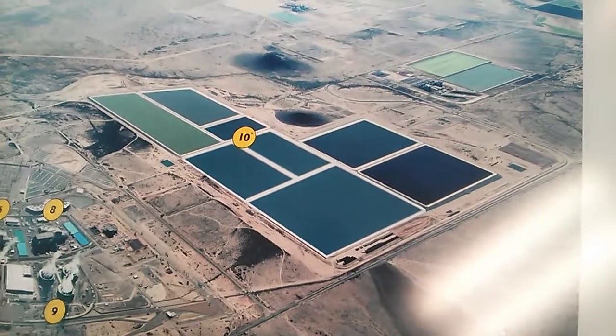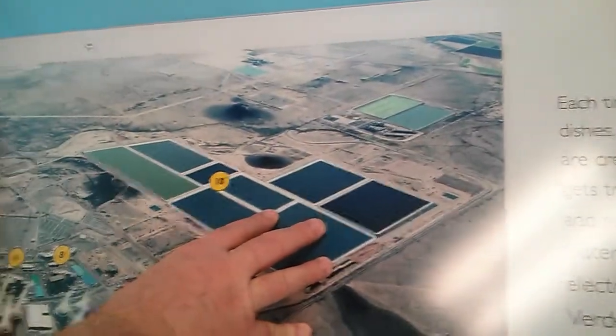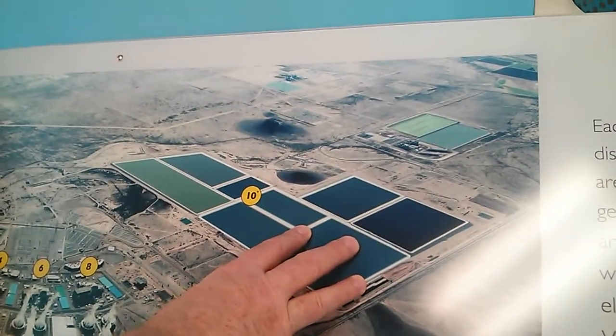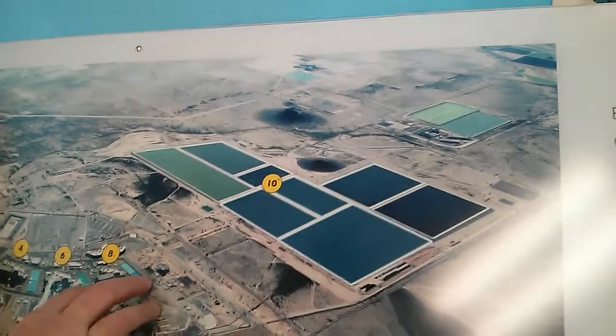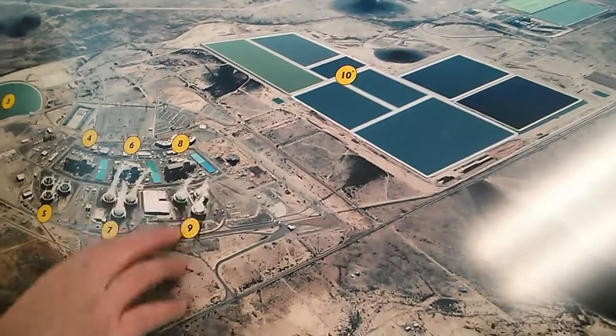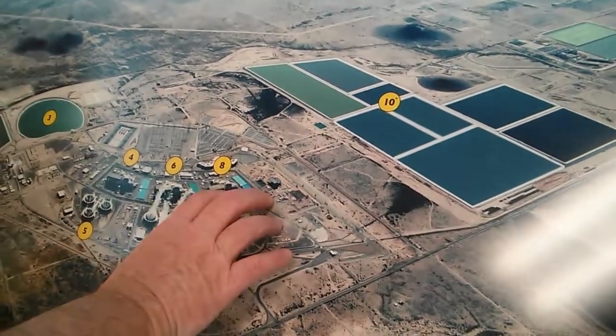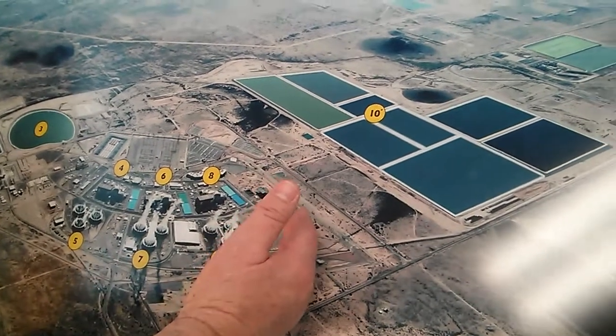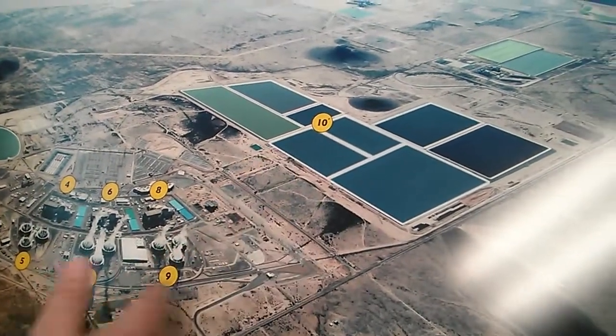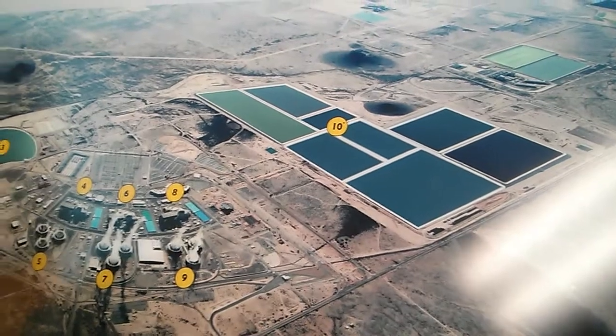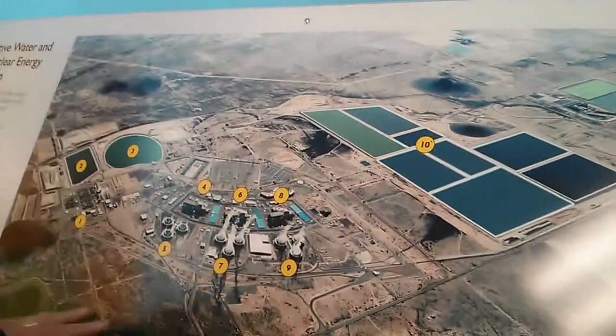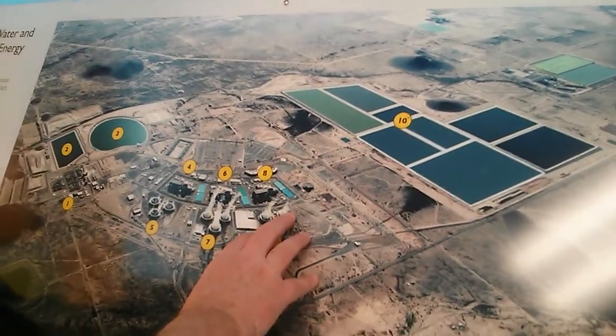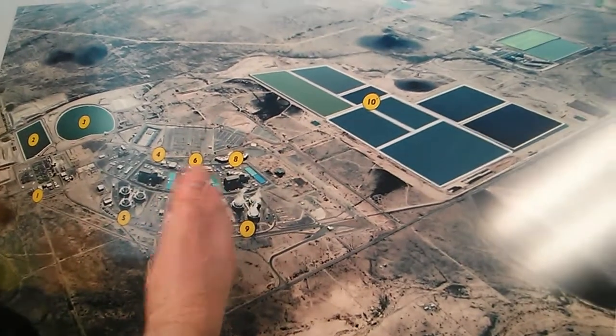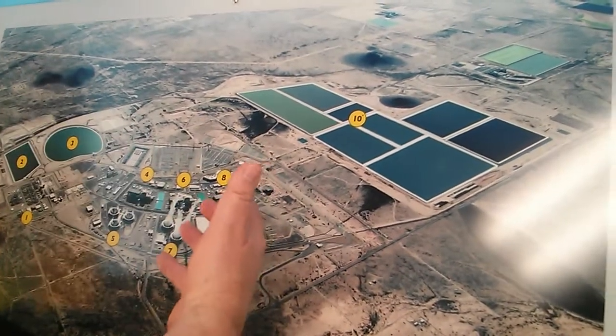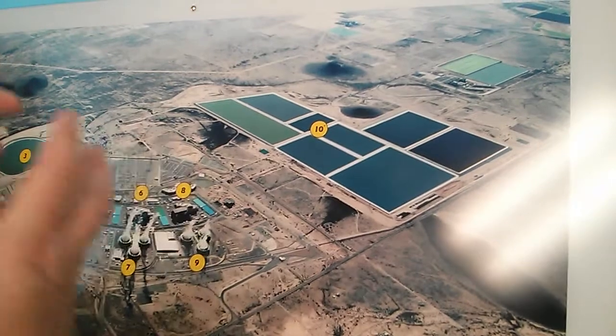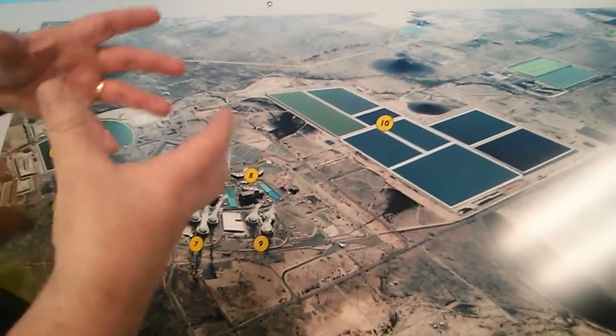At this point, the water is too heavily laden with minerals and salts because they've been concentrated. As you're evaporating 18,000 gallons a minute at one unit, you start with high levels of H2O. As it evaporates off, you're concentrating the minerals and salts in the circulating water. You don't want to continue that to the point where you're clogging tubes and potentially damaging equipment because the water's too heavy, if you will.